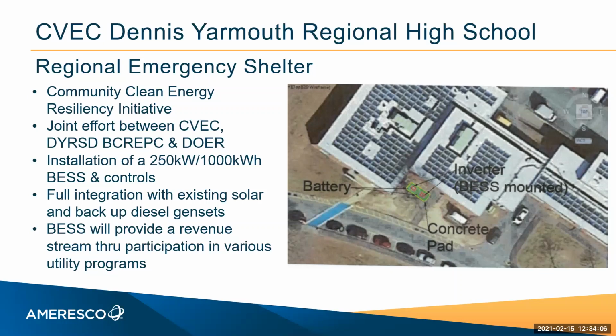Yes, so it's correct that when diesels are running below nameplate, the further down they go, they are losing efficiency, which inherently does require more fuel for the same energy output. But the math that was done at the time of analysis, the time of development, showed that while there is an efficiency loss with the diesel genset, the solar output is still a greater carbon reduction on a per kilowatt hour basis. Brian, does that make sense?